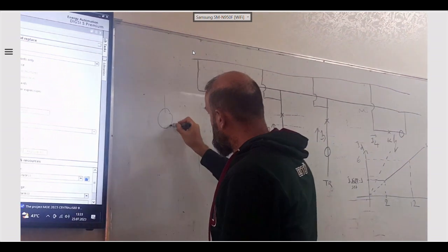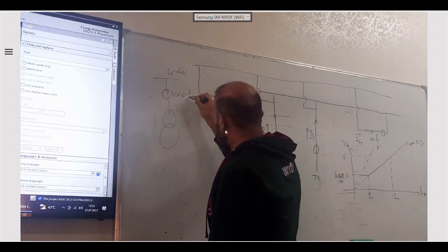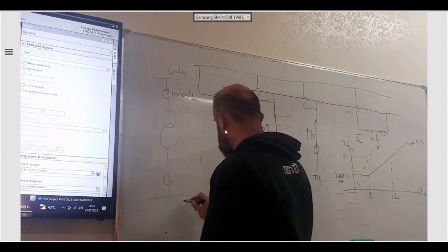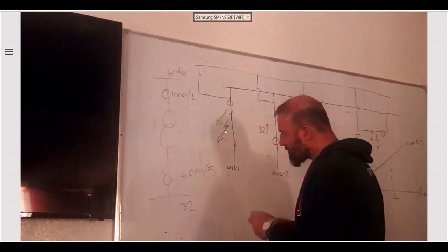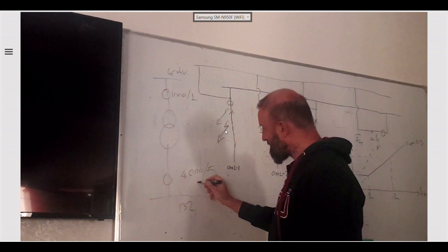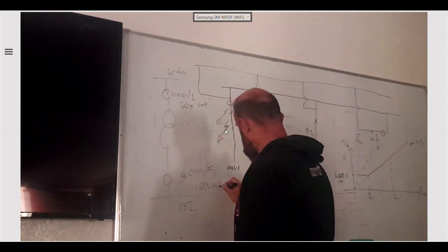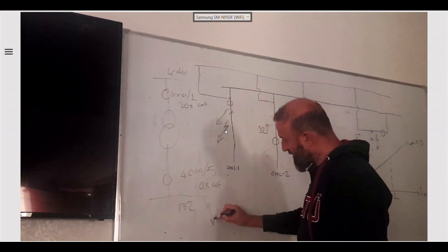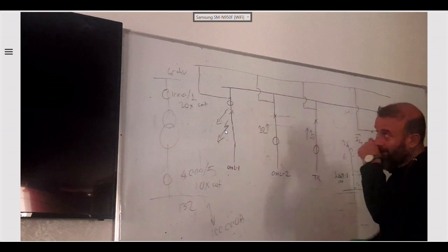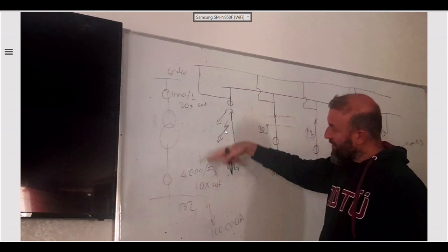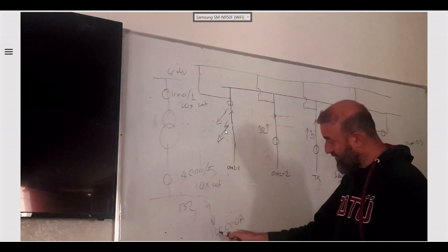We have this transformer. Say 400 kV CT here, 1000 over 1, another CT here, 132 kV, say 4000 over 5. And assume that this saturation is 10 times, this saturation is 20 times. If there is a short circuit here with a very high value, then what will be the values of the CTs' outputs? Is it exactly this value or is it less than this value? What do you think? If there is a real primary current passing through the line with this much current.